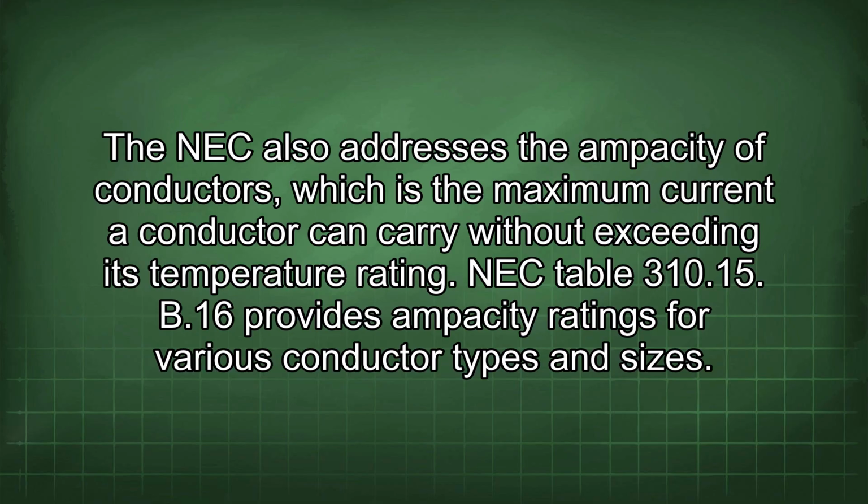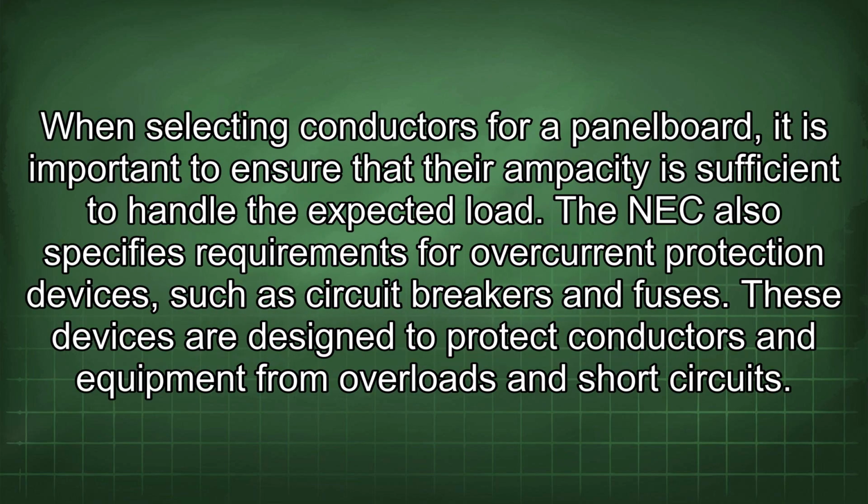The NEC also addresses the ampacity of conductors, which is the maximum current a conductor can carry without exceeding its temperature rating. NEC Table 310.15(B)(16) provides ampacity ratings for various conductor types and sizes. When selecting conductors for a panel board, it is important to ensure that their ampacity is sufficient to handle the expected load. The NEC also specifies requirements for overcurrent protection devices such as circuit breakers and fuses.